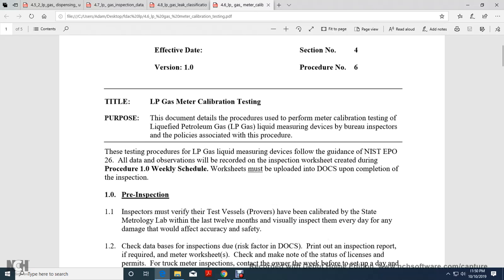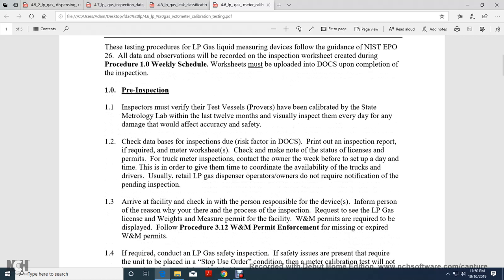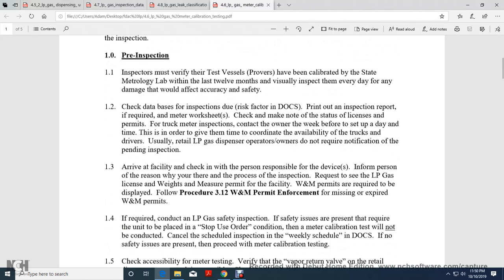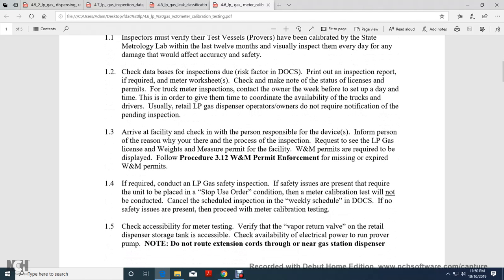Worksheets must be uploaded into DOCS upon completion of the inspection. Pre-inspection: the inspector must verify that the test vessels and provers have been calibrated by the state metrology lab within the past 12 months. Visually inspect them every day for any damage which could affect their accuracy or safety. Check the database inspection and the risk factor documents. Print out the inspection report with the required meter worksheet.